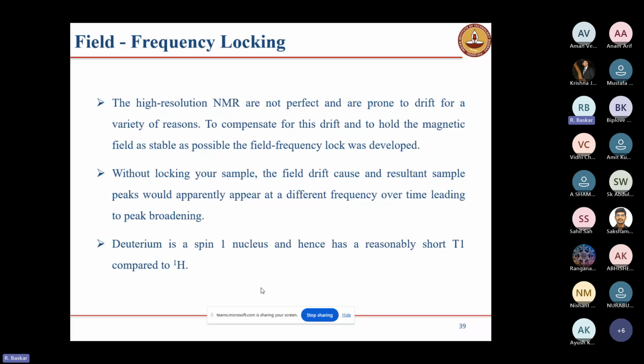For the drift adjustment, these lock coils are there. When the field is coming down, the lock coils will give additional magnetic field. It will make it constant. When the field is going higher, the same lock coils will reduce the field, acting like a resistor. It will reduce the magnetic field and make it constant. That is called field locking. For this field locking, the instrument takes deuterium as the reference, because we are using a deuterated solvent. This deuterium reference is taken, and it keeps the magnetic field constant. That is called locking.